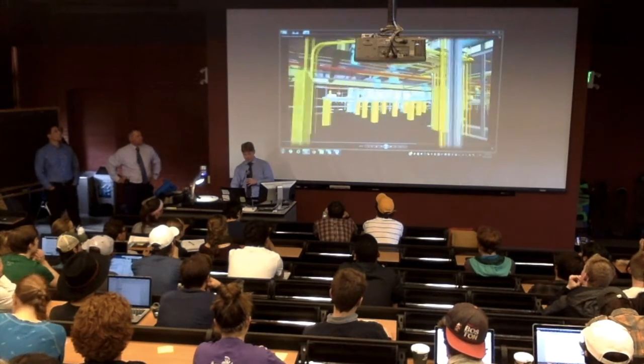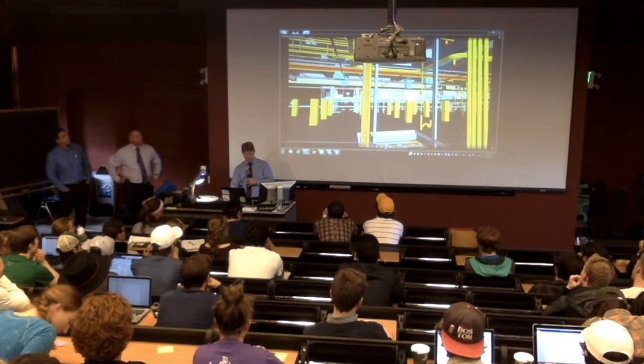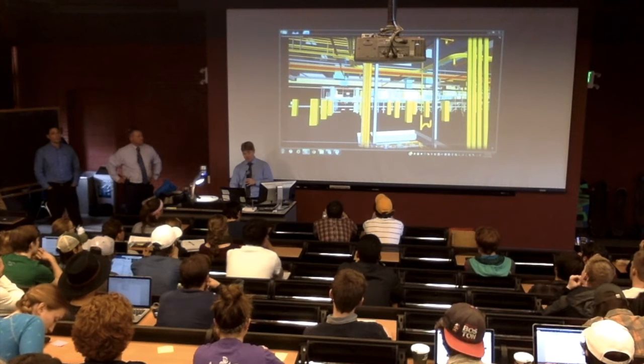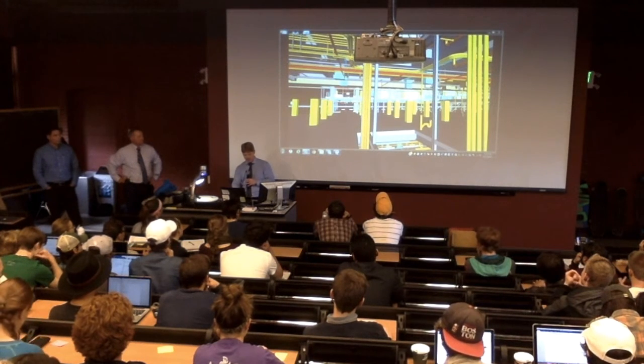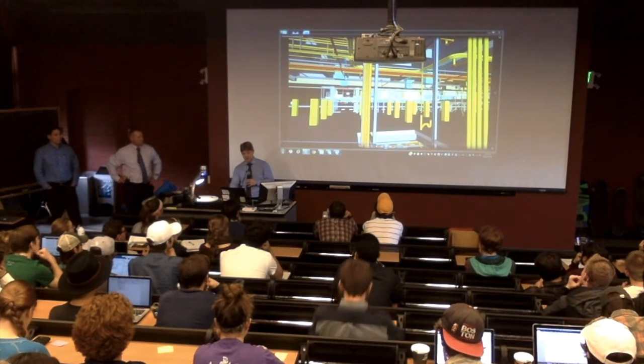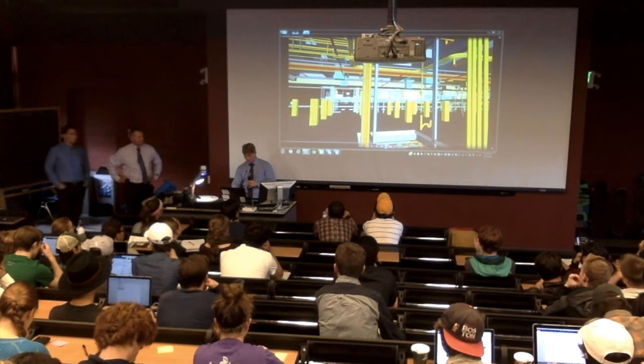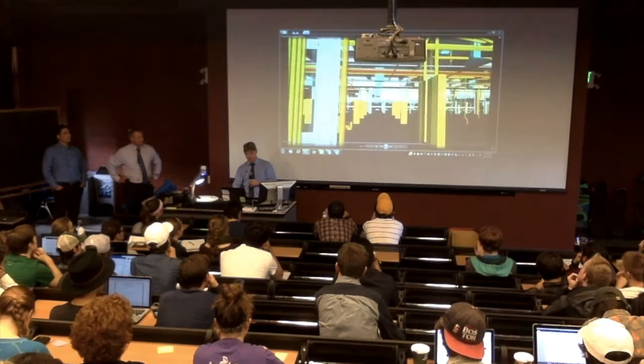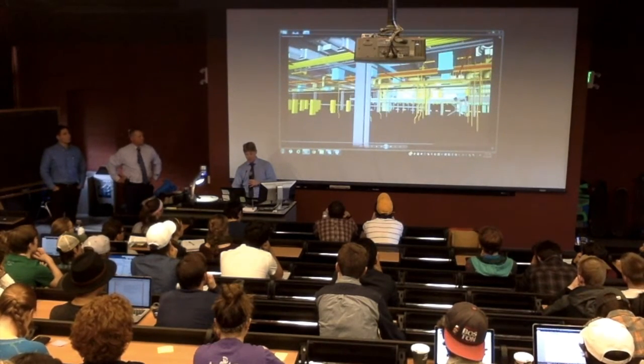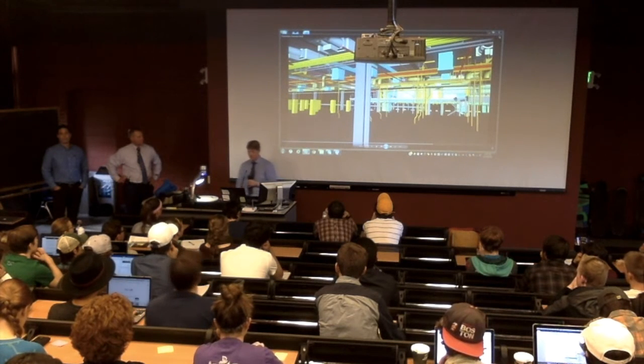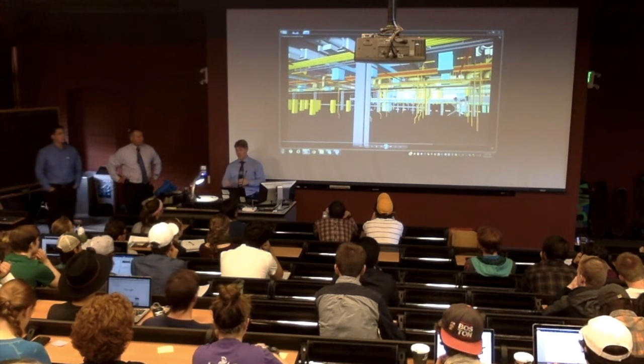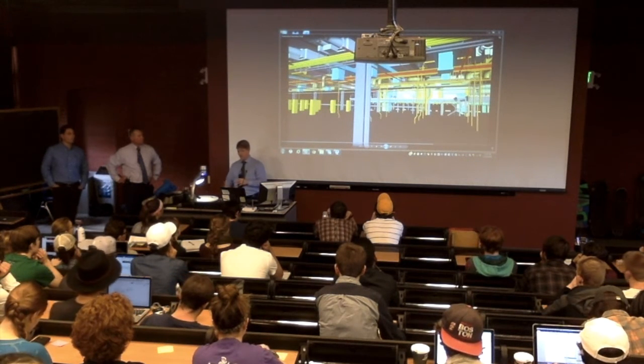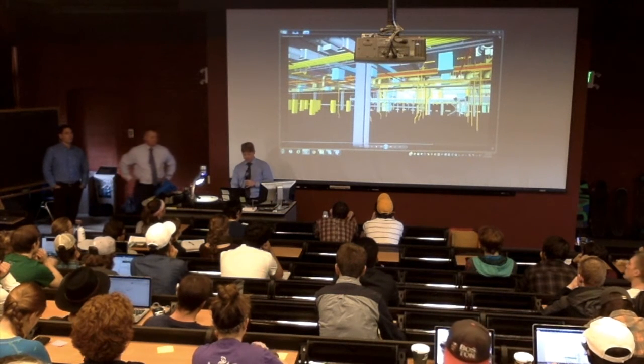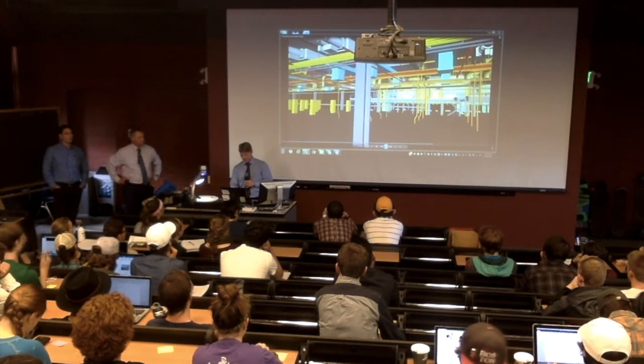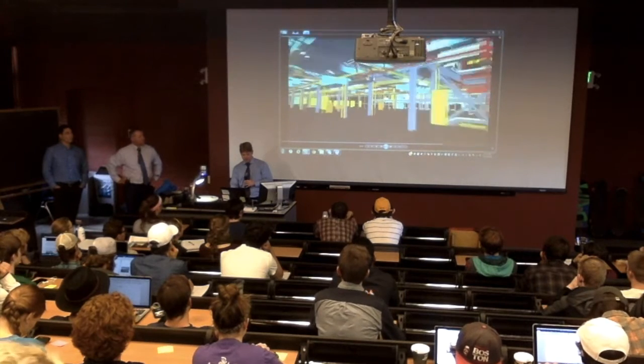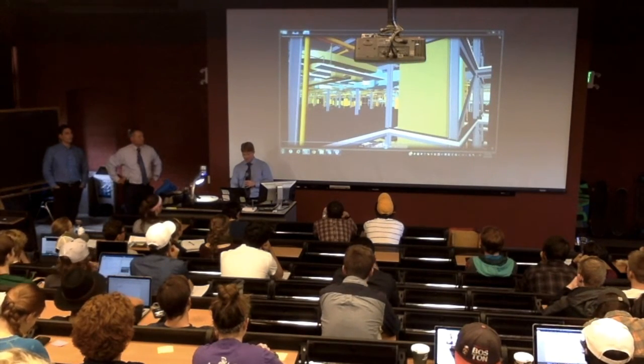So just going through the floor, again looking through where these would be walls that we're looking at. We've got multiple vertical pipe risers and conduit risers that all need to be coordinated, from what the voltage requirements are to feed all of the lab equipment, to the pipe size for all the particular cooling and heating needs on that floor. So again, this Navis simulation is a good tool to look at how this stuff actually works. And we'll run a clash detection. You might even see a couple in this model to draw our attention to where some of the big hits are, where things aren't going to fit through the corridors of the building. And if it doesn't work, then we got to move the stuff out into the labs. So that's kind of the process we go about as mechanical, electrical, plumbing engineers. We're looking at everything, how it fits together.